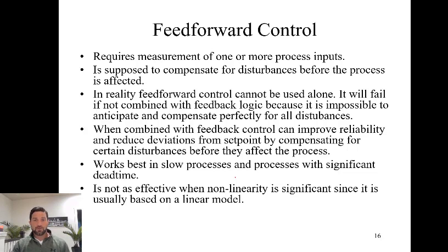Feed-forward control requires an additional measurement, which costs money. So feed-forward control is going to require additional sensors and controllers to measure one or more inputs. The purpose of feed-forward control is that it compensates for a specific disturbance before it affects the process. In reality, feed-forward control cannot be used alone. It has to be incorporated with feedback control because there's no such thing as perfect logic, perfect control of the system, or perfect metering in order to prevent a process from reaching its constraint.